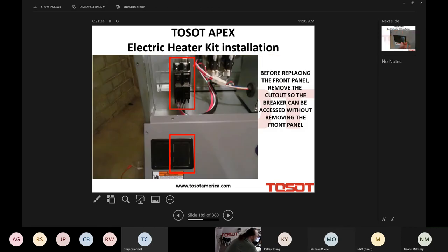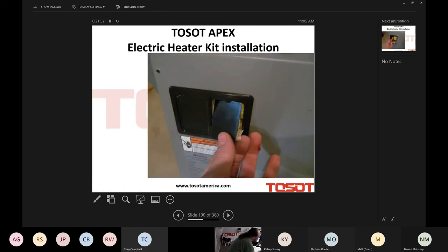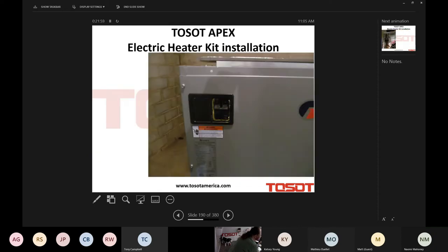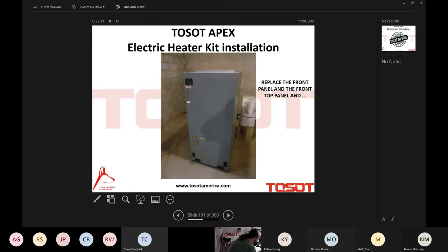The last thing we want to do as we reassemble the cabinet, putting the front panels back on, we need to cut out, in this example, because this is the 10 kW. Yep, this is the 10 kW that I used. I just have the one breaker, so I need to knock out the knockout provided on the front panel of the Apex indoor unit. And now that provides you access to the breaker without having to remove the front cover. Beautiful thing, isn't it? Absolutely. And there, again, is the final product.